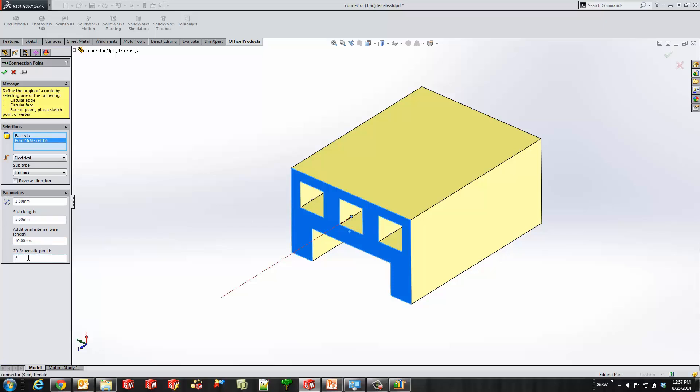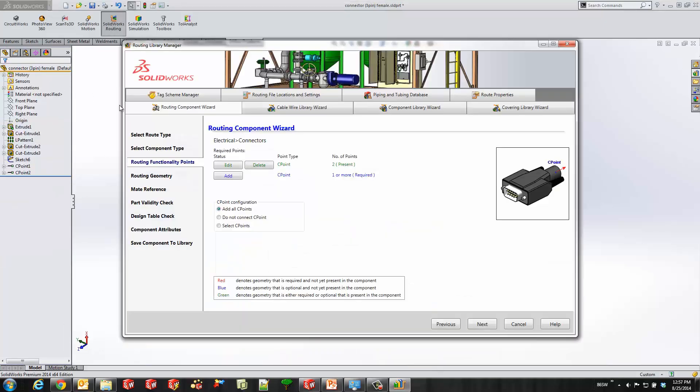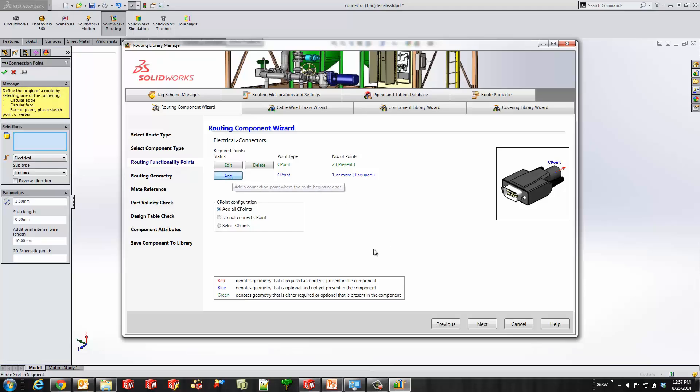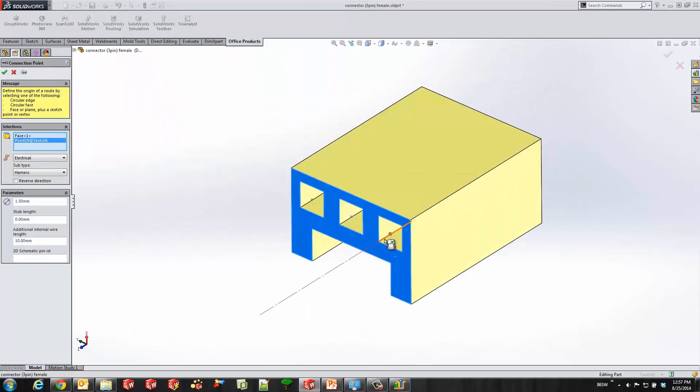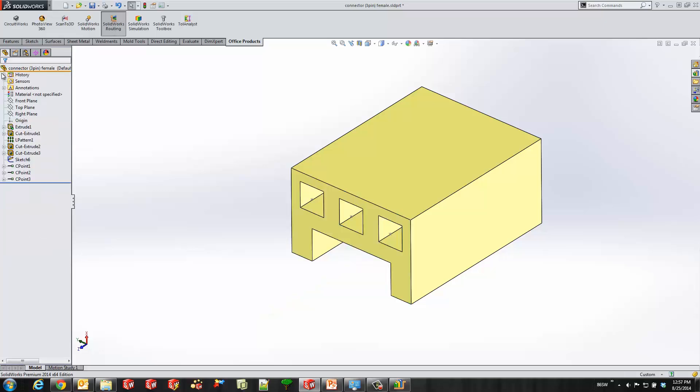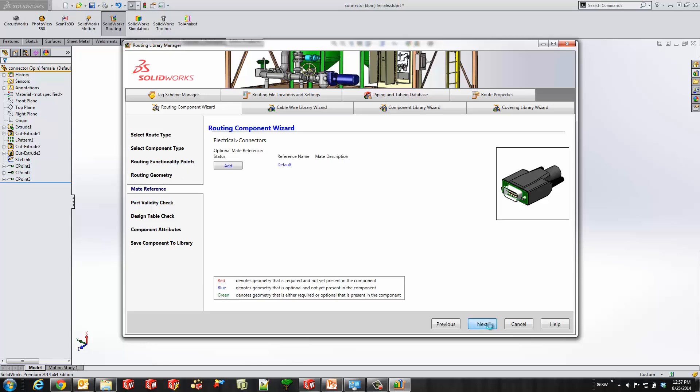So we'll see that again come up later. Also, you might see that we have a field for how much additional internal wire. So when we really route these cables and wires, we get really accurate calculations for our wire lengths. I'm going to go ahead and finish this third one up real quickly. And we'll label this last schematic pin ID. So you could keep adding more if you had more pins, but we only have a 3-pin connector, so that's perfect.